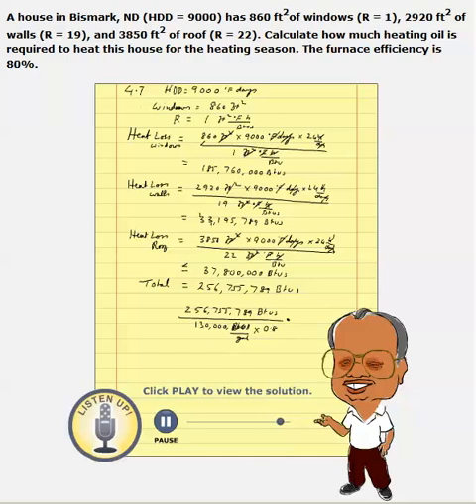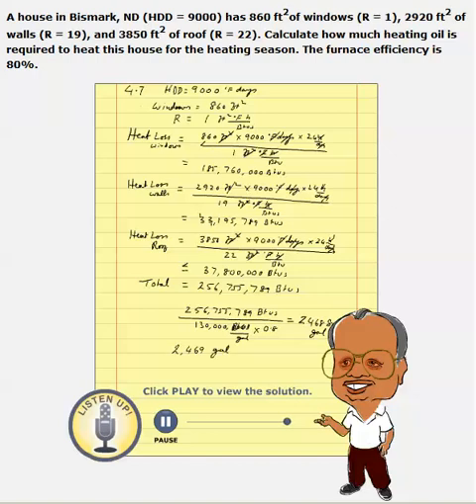The efficiency is given as 0.8, so only 80% of this will really be available as heat, making the requirement a little bit higher. Doing this calculation, it will be approximately 2,468.9 gallons of oil required to heat this place.